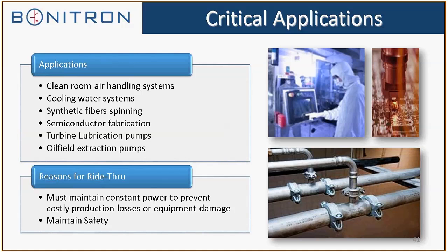Cooling water systems: the chill water that goes to the machine tools for the wafer etching has to be consistent. There can't be any change in flow to the machine tool, or the machine tool will detect that minute change and shut down. When it shuts down in a clean room, all of the products in the clean room have to be disposed of. They're considered scrap products. They don't even worry about testing them, they just pitch them out. So that's why you have quite significant losses in a lot of critical applications.